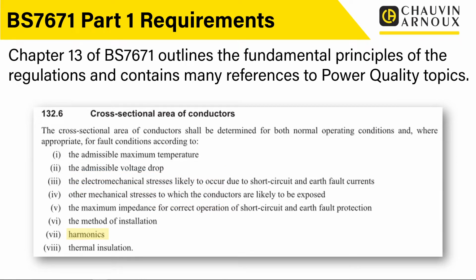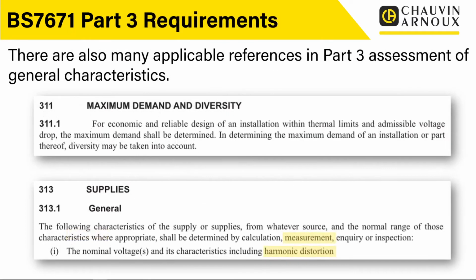Now, I did mention earlier on about actually working out the cross-sectional area of conductors, doing cable calculations. And again, we talk about admissible temperature and volts drop and all those sort of things. But down the list, you'll see number 7 there is actually harmonics. And we will touch on a couple of examples later on in the webinar of how to actually calculate cable cross-sectional areas allowing for harmonics, because that is included in appendix 4. It is in there, so we'll actually touch on that. But again, how many people actually do that? I'm guessing that's very few at the moment, and we need to change that.